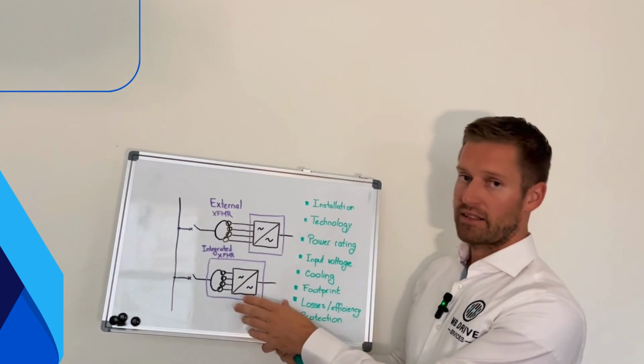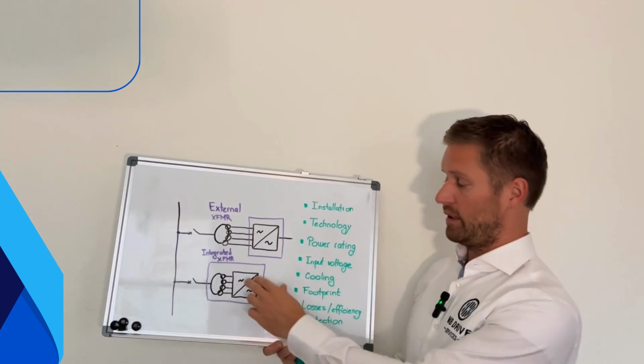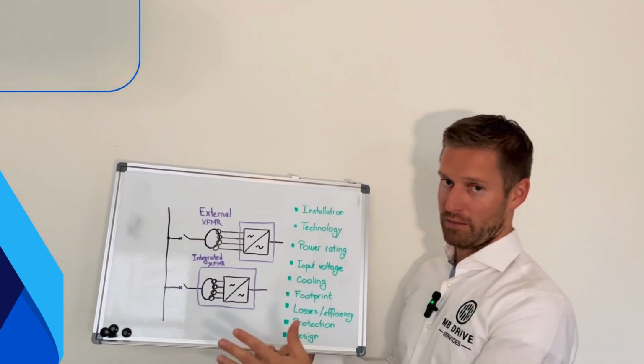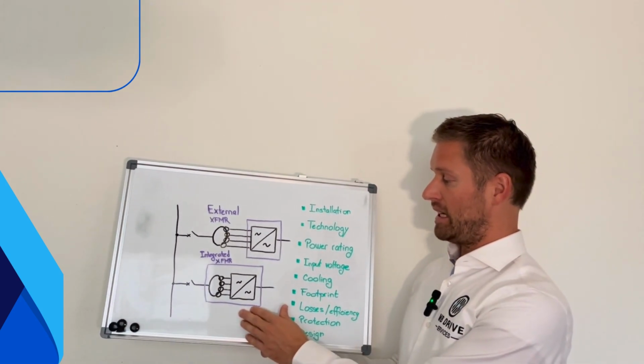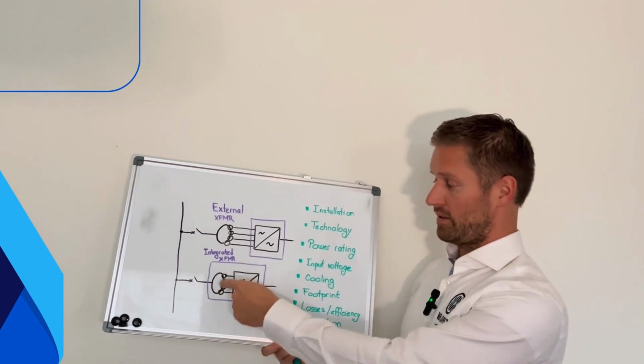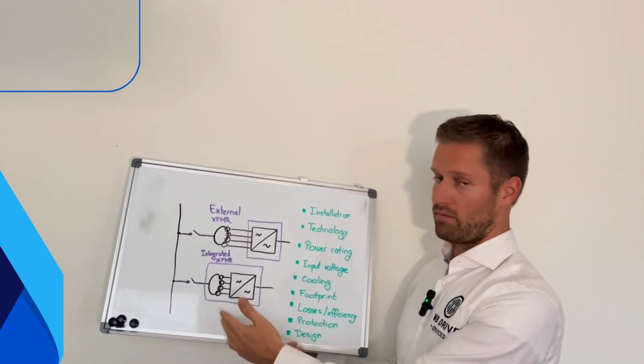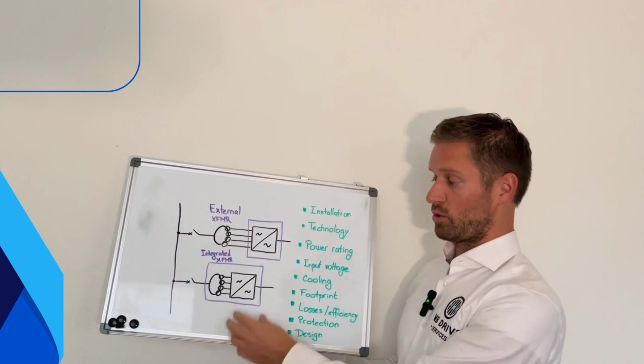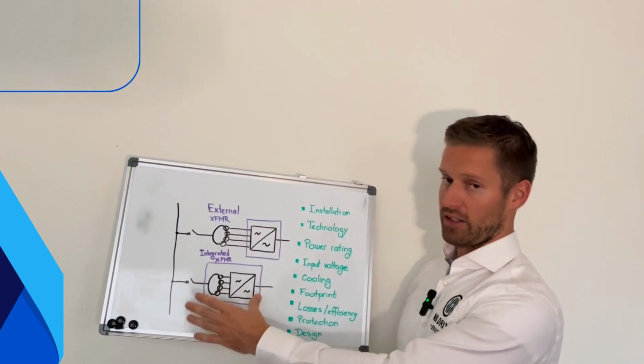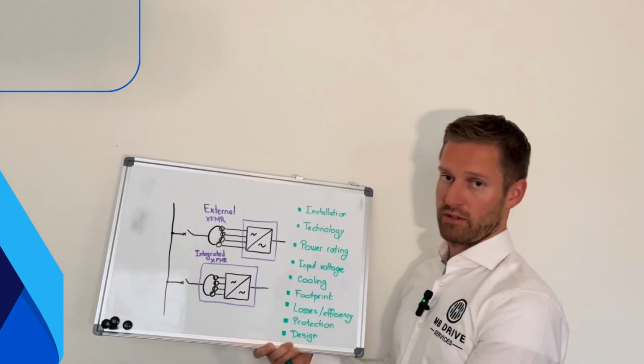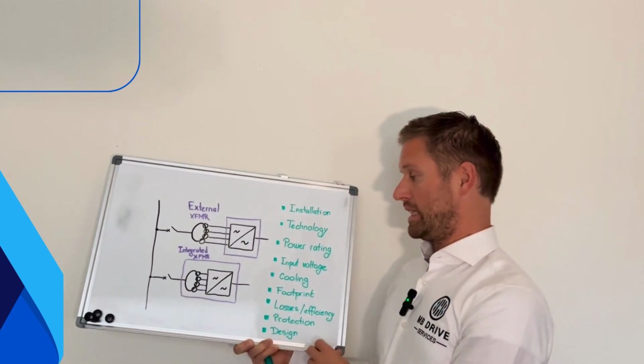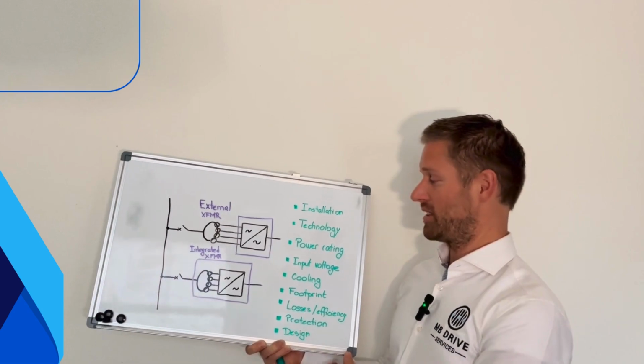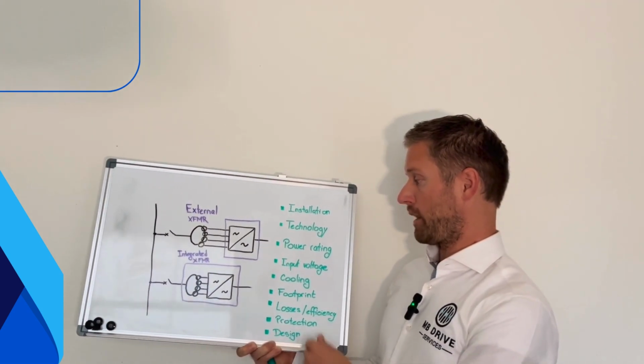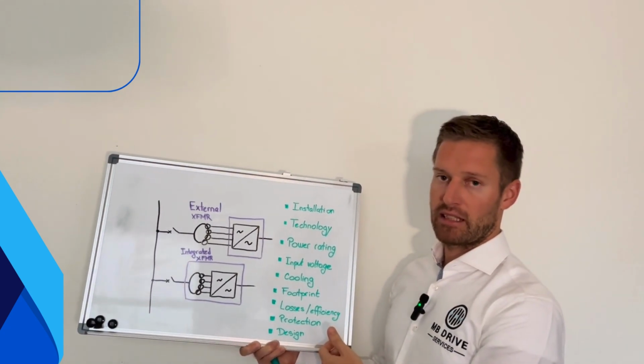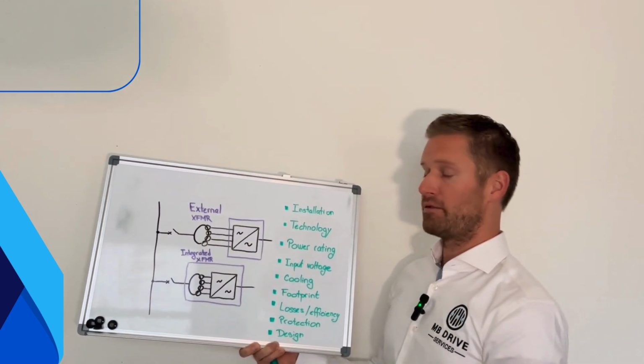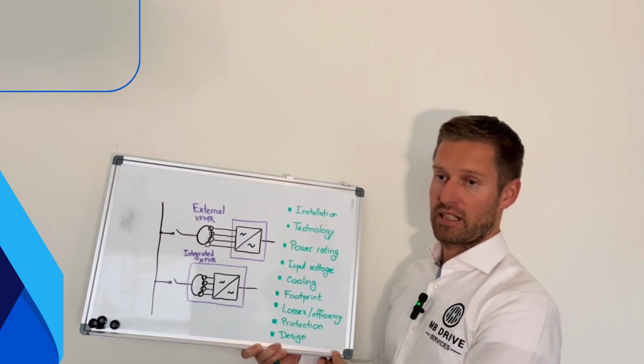Regarding power rating, the integrated transformer is limited in power. It's because it's inside the VFD enclosure, so there are some dimension and space restrictions, and also because the losses of the transformer, this dry type, normally for most of the solutions I have seen, go into the electric room. So having a large integrated transformer would also mean a large heat load for the electric room, which is not so easy then for the system integration. For the external transformer, there is virtually no power limit, so we can have a transformer of 100 MVA or more if we have such a large VFD that requires so high power.